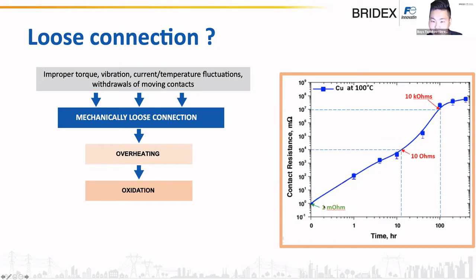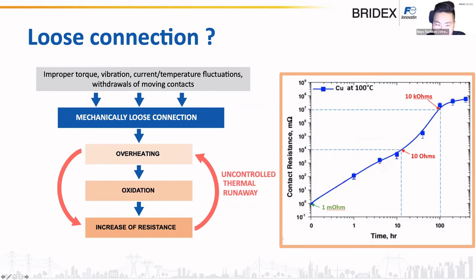Here on the graph, you can see the copper contact connection, and the contact resistance at the initial time is only 1 milliohm, which is totally fine. But after 10 hours at 100 degrees conditions, the resistance increases dramatically and becomes 10 ohms, which is a huge value for a contact connection resistance. So the oxidation accelerates the growth of resistance, and this increase of resistance causes even stronger overheating, and stronger overheating provokes even more resistance, and you start to have this uncontrolled thermal runaway, which in the end will lead to a fire.